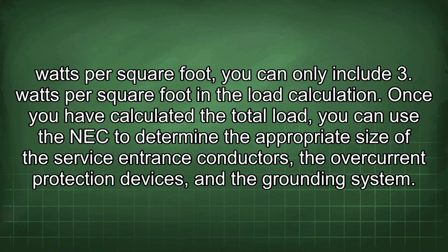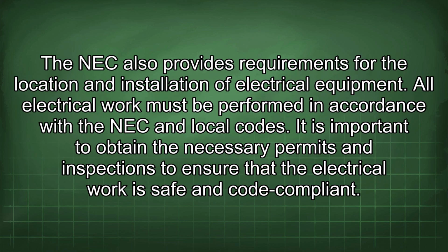Once you have calculated the total load, you can use the NEC to determine the appropriate size of the service entrance conductors, the overcurrent protection devices, and the grounding system. The NEC also provides requirements for the location and installation of electrical equipment.